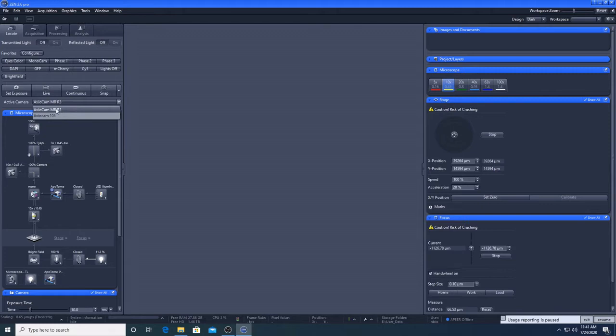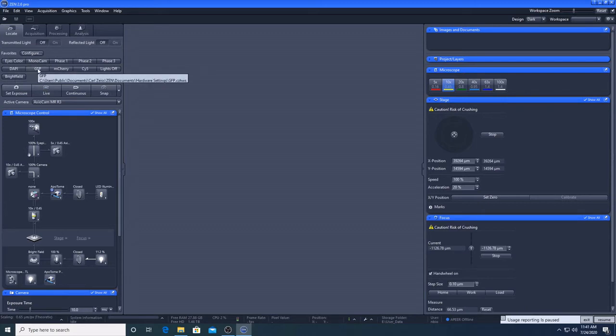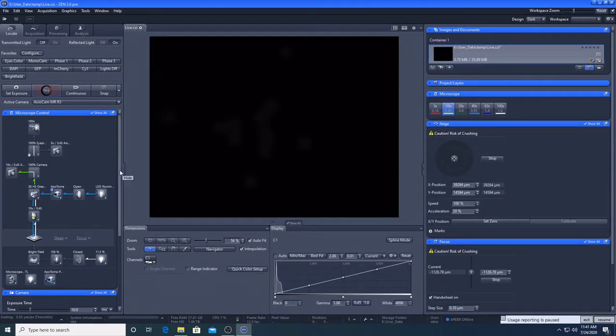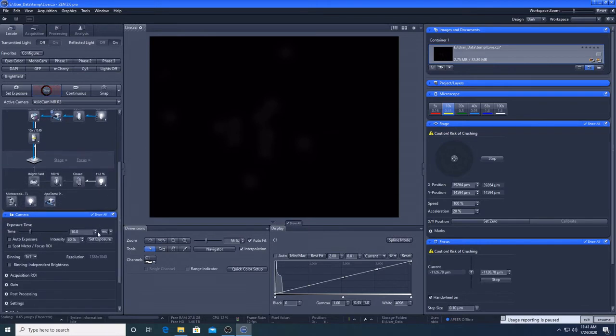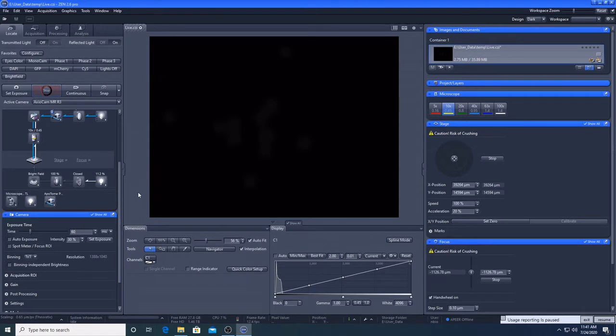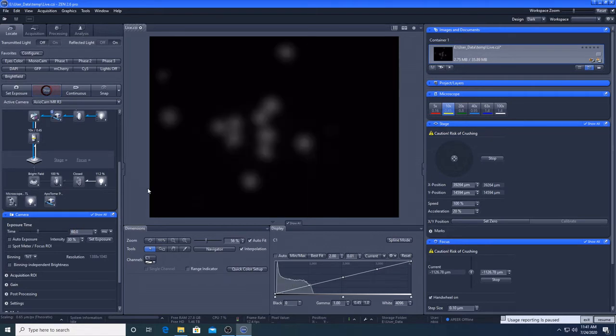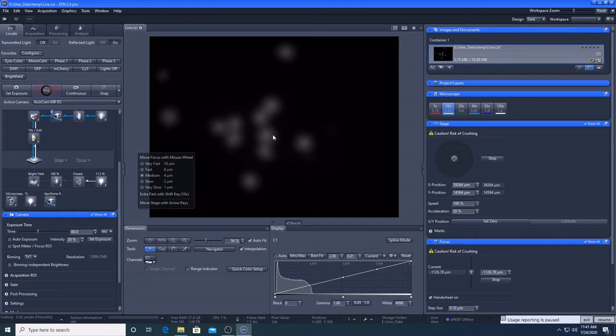I will now show you an example of how to find your sample using this setup in the locate tab. I am going to select the black and white camera in the GFP channel and go live. I can adjust the exposure time here. The image is a bit dull so I will increase the exposure time a bit to get a better look. I can adjust the focus either using the wheel on the microscope or I can press control on the keyboard and move the mouse wheel.